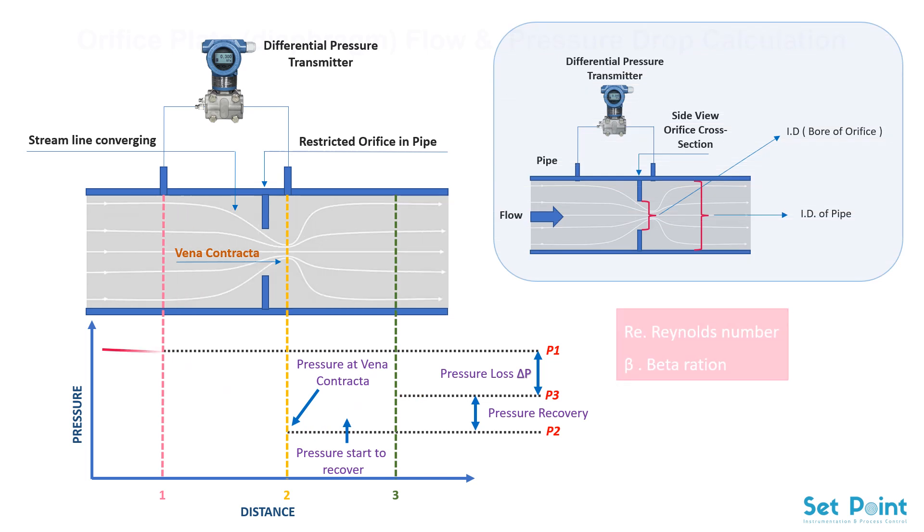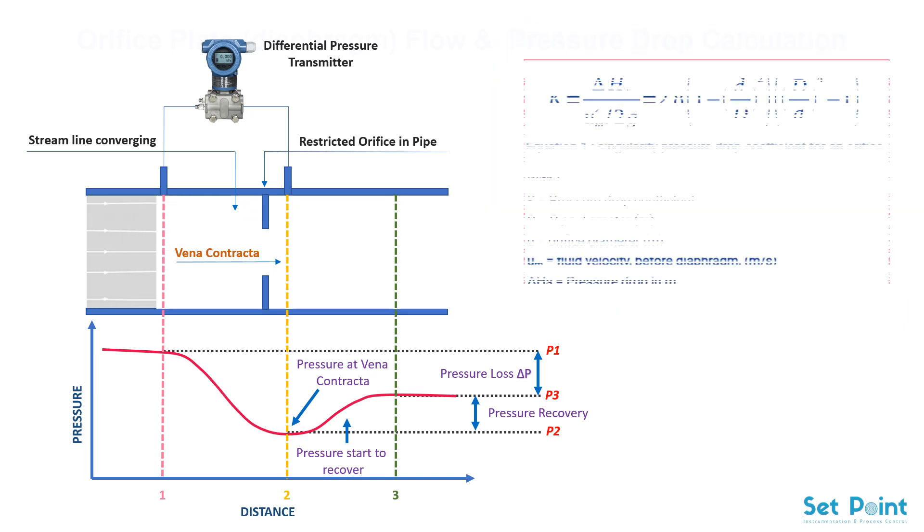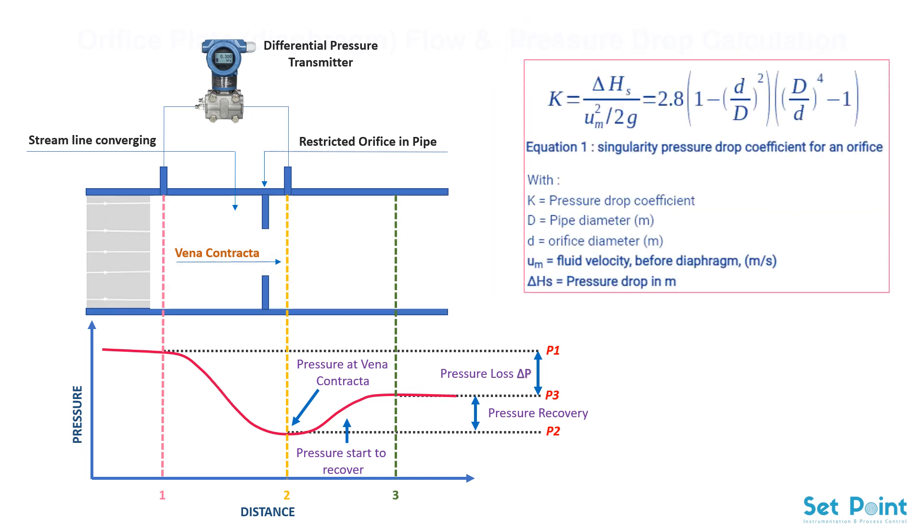Pressure drop across orifice is mainly affected by Reynolds number and beta ratio. The following correlation is given by Gibson, it is reproduced in many books. It relates the flow through the orifice and the pressure drop.